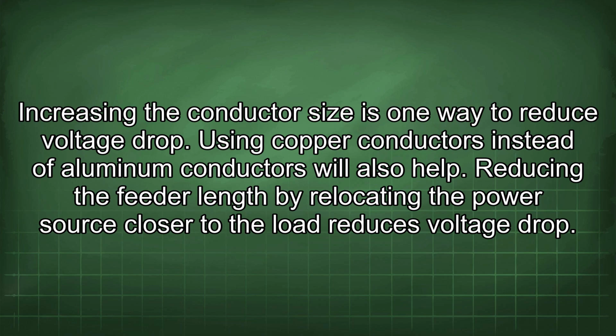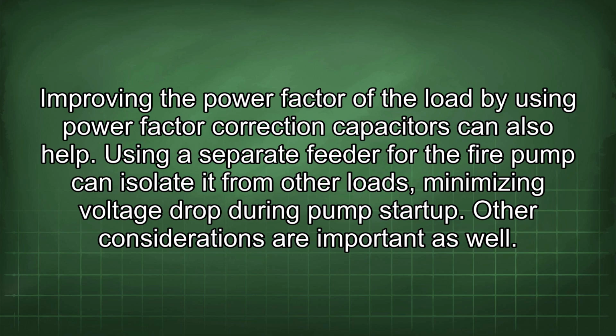Reducing the feeder length by relocating the power source closer to the load reduces voltage drop. Improving the power factor of the load by using power factor correction capacitors can also help. Using a separate feeder for the fire pump can isolate it from other loads, minimizing voltage drop during pump startup. Other considerations are important as well.